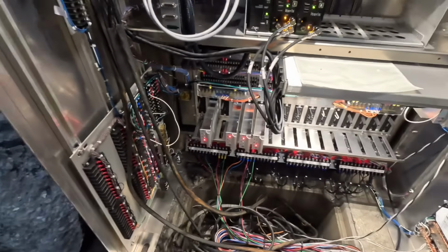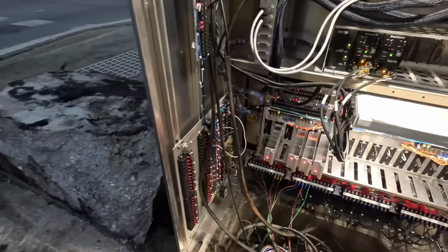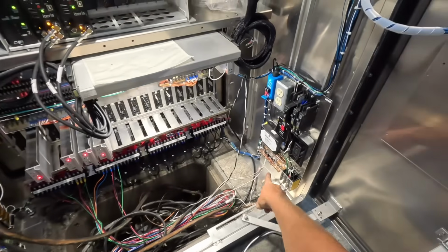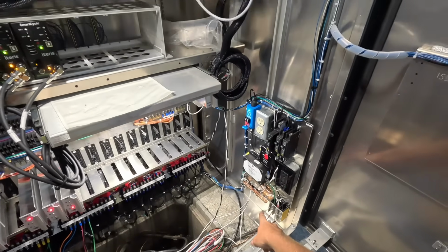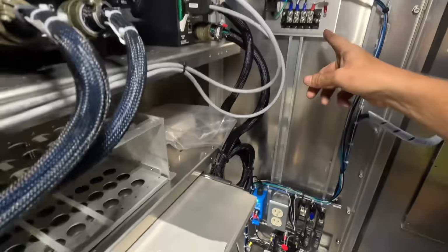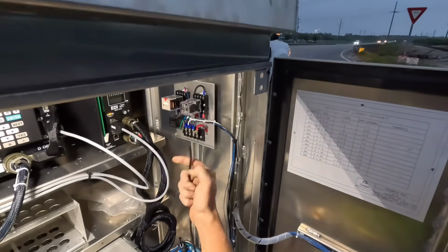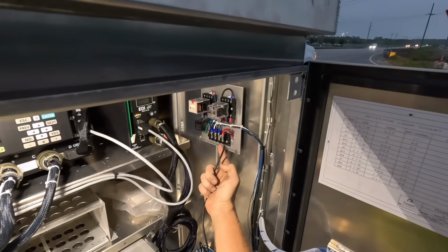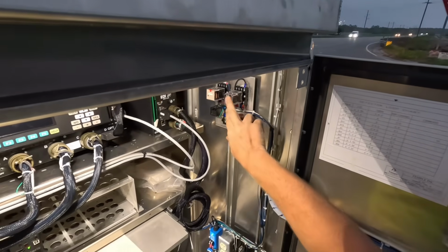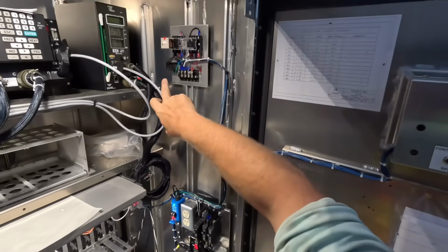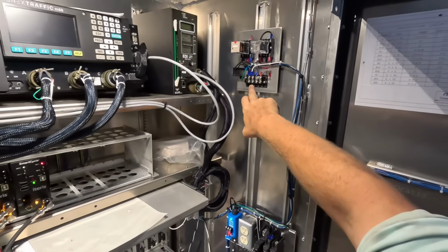So let's get right into that stuff. Whoa, guys, it's starting to get a little dark out here on me. But this cable right here, again, is going to the blank out sign. I'm gonna go ahead and untwist these ones because the white's gonna land down on our neutral block. And then the positive, the hot side, is gonna land here on this pin right here, pin number 4. And when this relay closes here, and I hope y'all can see not just the top of a cabinet, but when this relay closes, it's gonna feed power onto here.